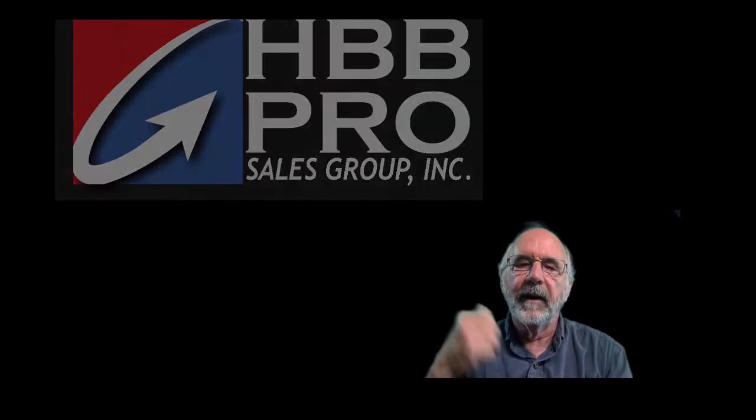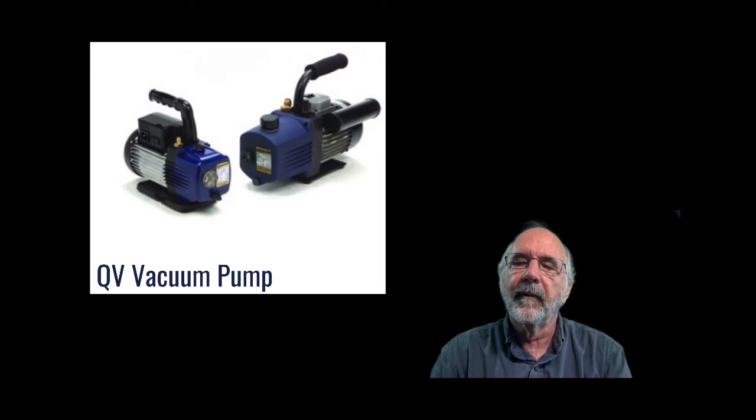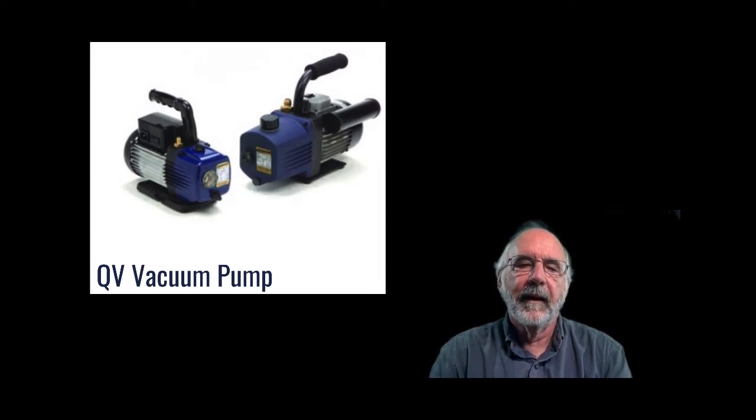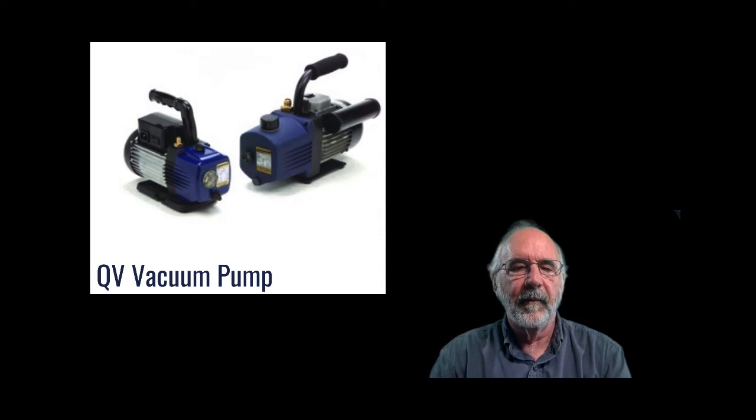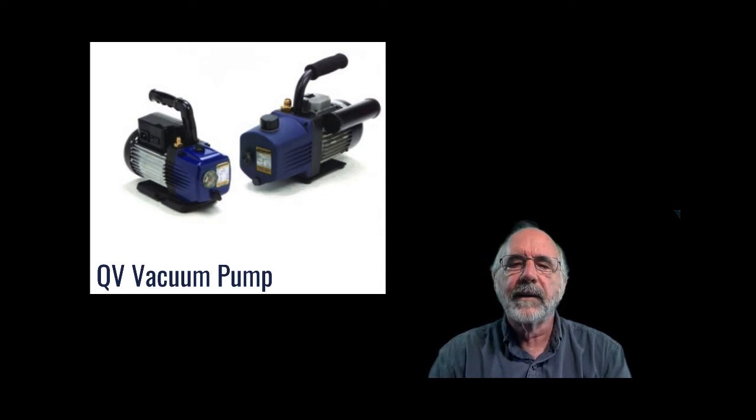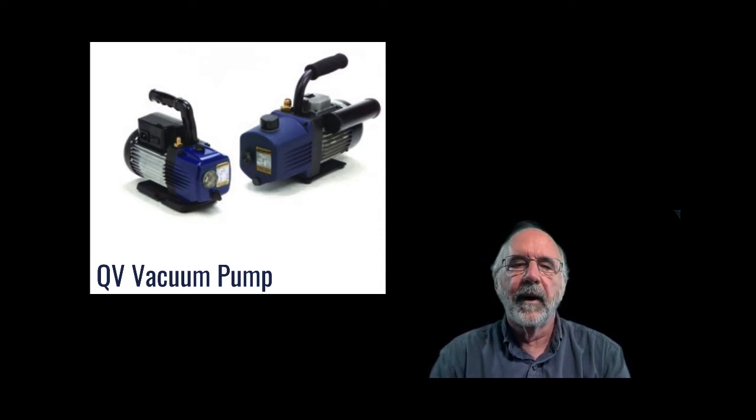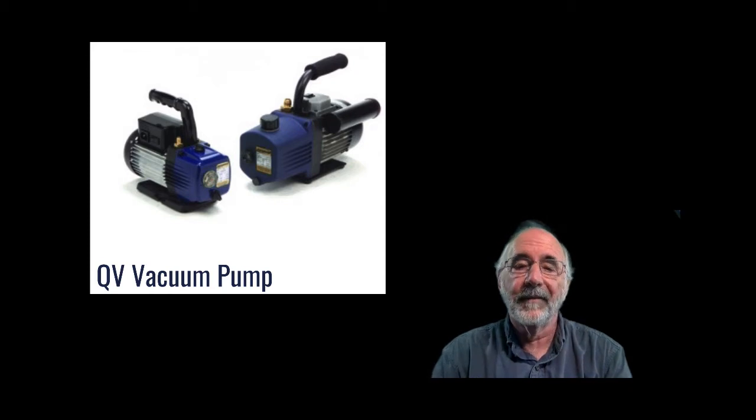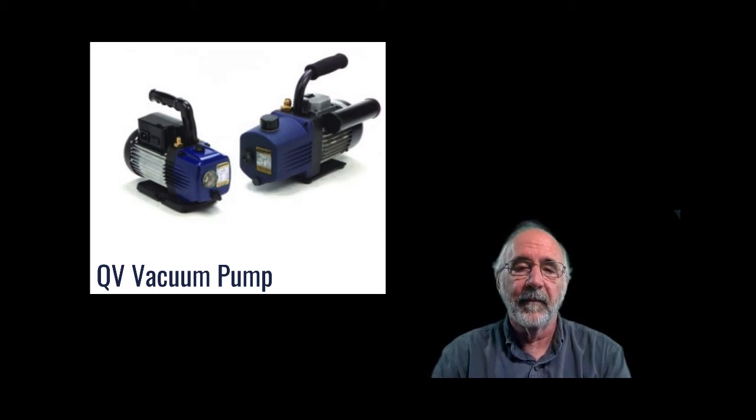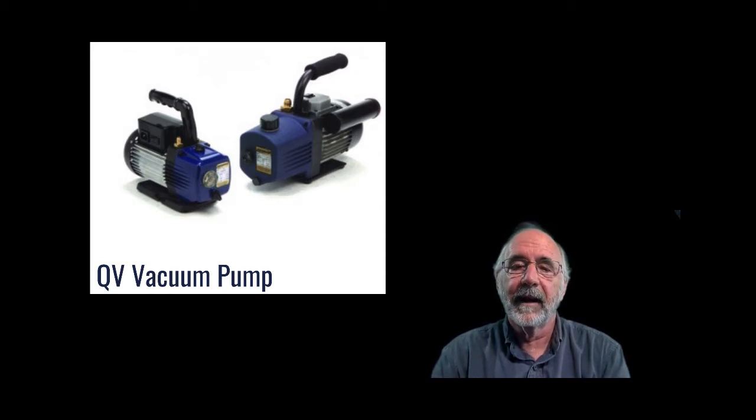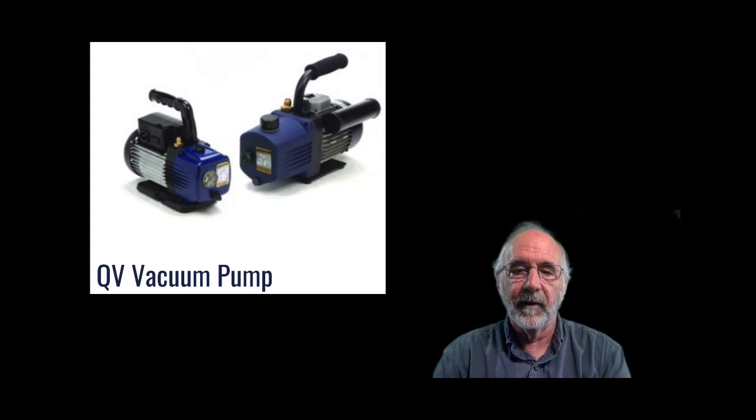Behind me here are two Bacharach vacuum pumps, one rated at 1.7 CFM, the other one rated at 5.3 CFM. In theory, the 1.7 CFM pump will be able to handle up to a three or four ton unit. The 5.3 CFM pump should be able to handle up to a 28 ton piece of equipment.